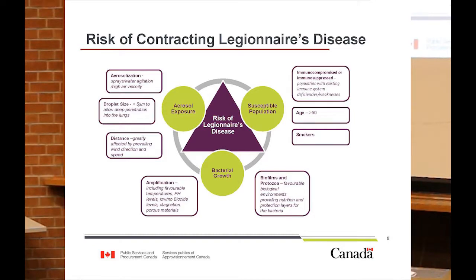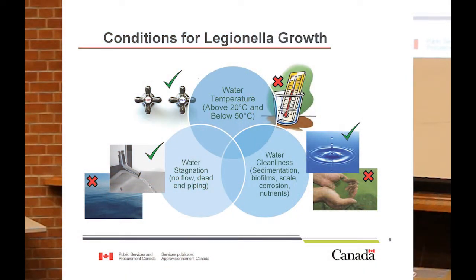So what are those conditions for Legionella growth? Legionella likes to grow between 20 and 50 degrees Celsius. Below that it's more in a dormant state, and above that you would start to have a kill rate on the bacteria. Also, water cleanliness: you want to make sure you're not having a lot of sedimentation, scale, biofilms, or nutrients in your water that can feed bacterial growth.